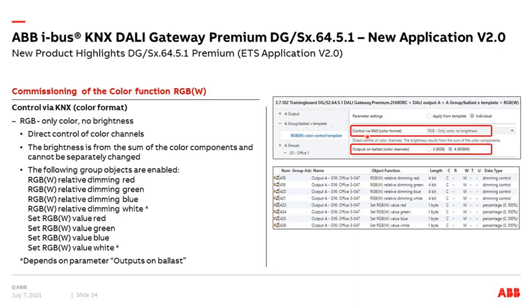When you select RGB color only (no brightness), you directly control three or four channels depending on the next parameter. You can select RGB or RGB white — if RGB white, you get four objects for dimming (4-bit dimming) for red, green, blue, and white, plus four 1-byte objects (0–100%) for setting the value of each channel. This allows use of a standard control element or push element for dimming or sending a value to control the LED strips.